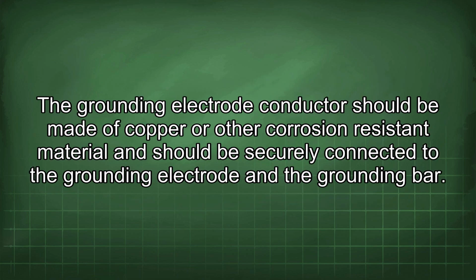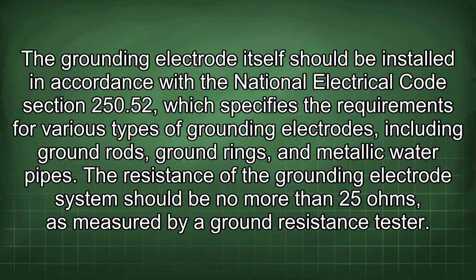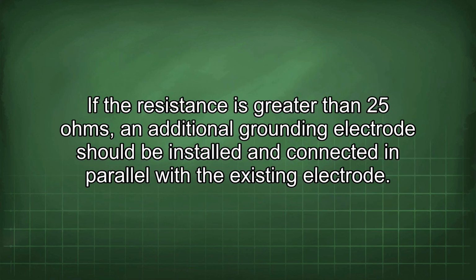The grounding electrode conductor should be made of copper or other corrosion-resistant material and should be securely connected to the grounding electrode and the grounding bar. The grounding electrode itself should be installed in accordance with the National Electrical Code Section 250.52, which specifies the requirements for various types of grounding electrodes, including ground rods, ground rings, and metallic water pipes. The resistance of the grounding electrode system should be no more than 25 ohms, as measured by a ground resistance tester. If the resistance is greater than 25 ohms, an additional grounding electrode should be installed and connected in parallel with the existing electrode.